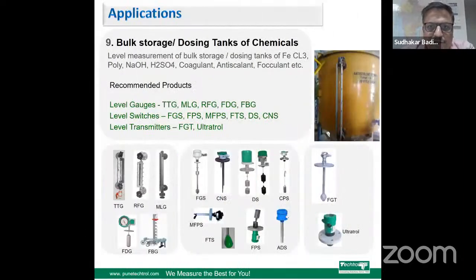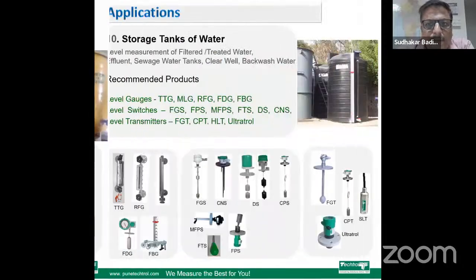These are some bulk storage tanks where level gauges, level switches, and level transmitters can all be used. For visual indication, you can see tubular level gauges installed. Level transmitters we already explained, like ultrasonic or hydrostatic, or float guided. Switches depend upon the application, like float guided, displacer, and capacitance.